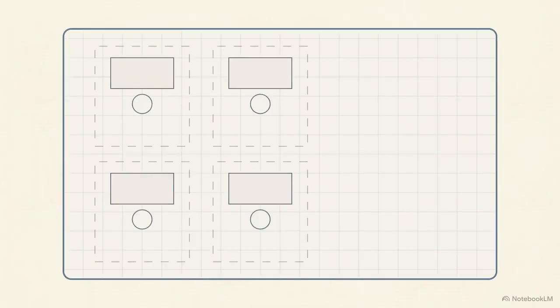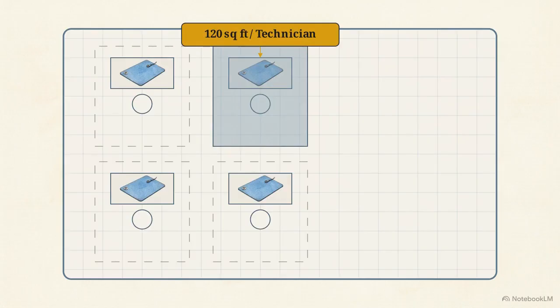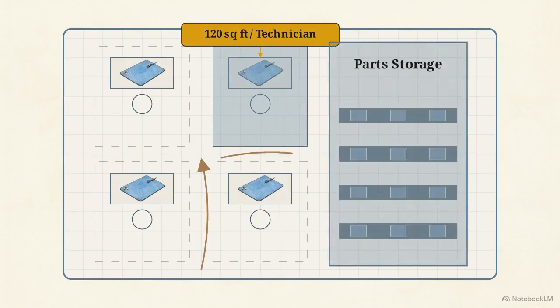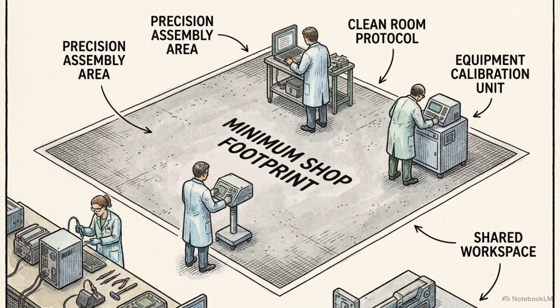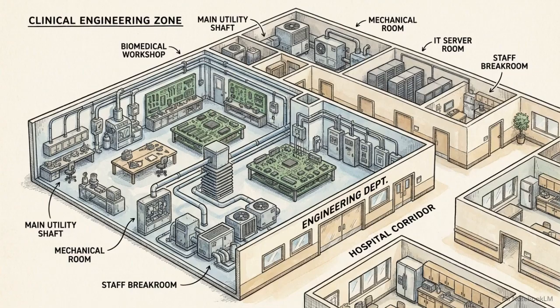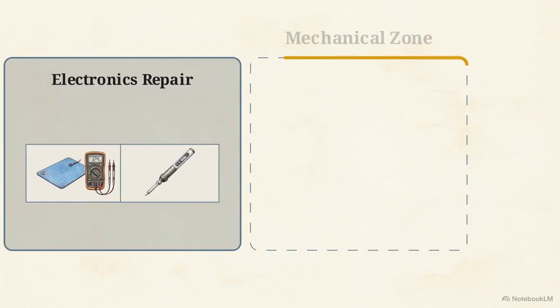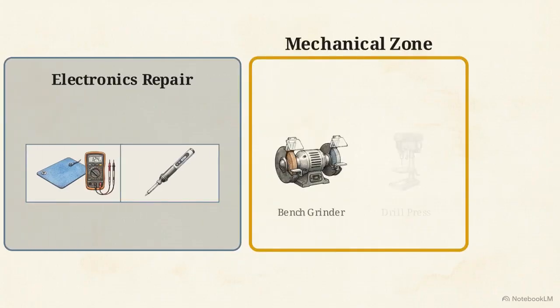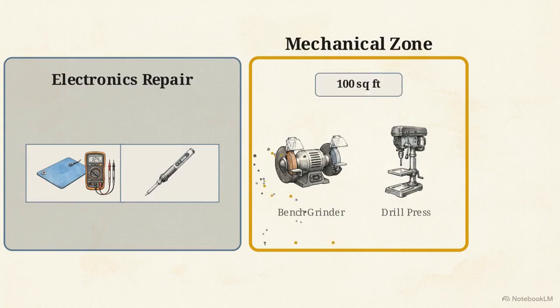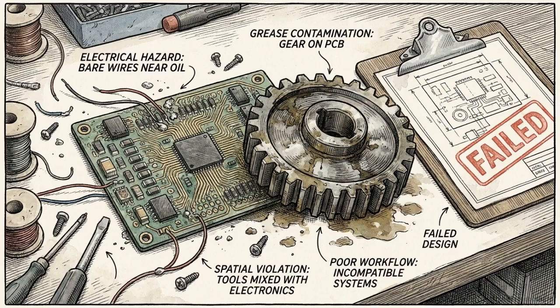Moving into the main shop, industry standards mandate a strict minimum of 120 square feet per technician, plus dedicated space for part storage. This means a team of 4 technicians demands a footprint of over 400 square feet. This department cannot be tucked into a leftover closet. It requires a primary hospital placement. You also have to include an isolated mechanical zone. Heavy fabrication tools like bench grinders and drill presses require a separate space to keep metal shavings away from delicate electronic repairs. Compromising on this square footage results in overlapping clean and dirty zones, a direct violation of Joint Commission audit standards.